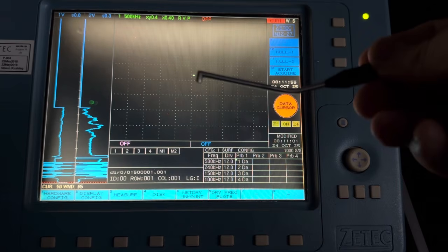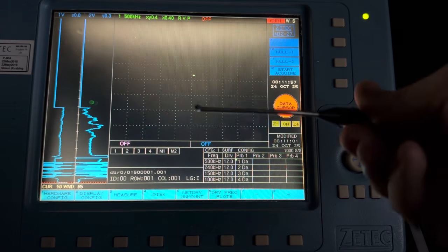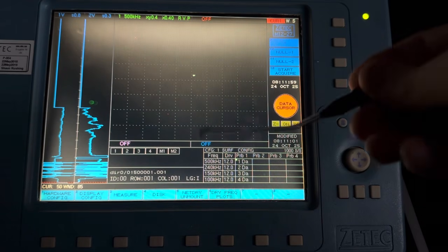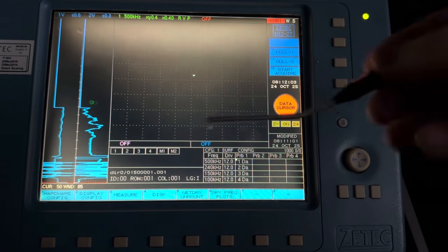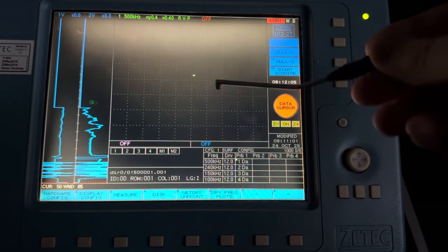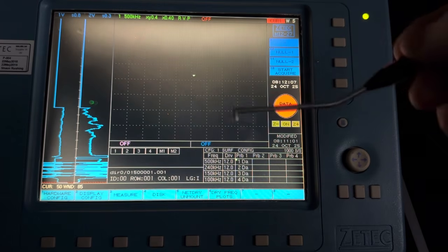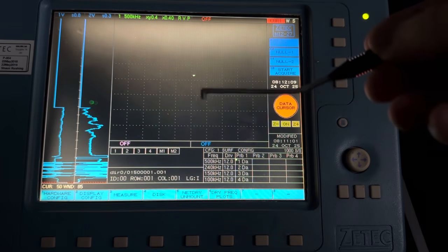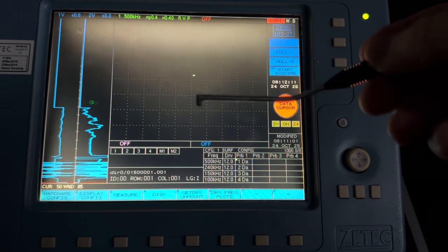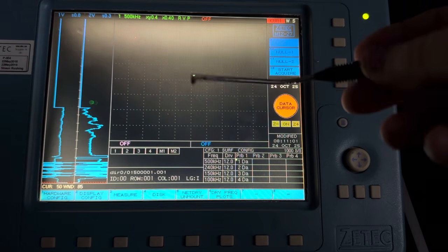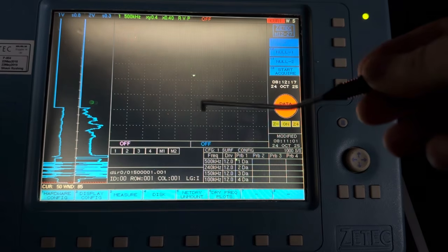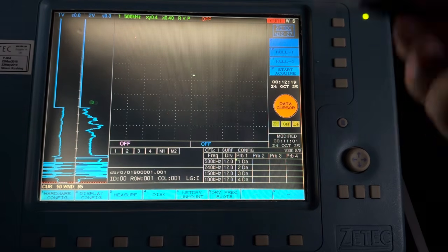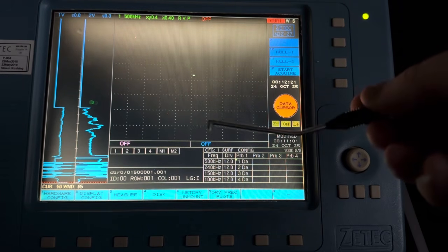for discontinuities. But with a pancake coil, as long as you're scanning properly with 100% coverage and you're hitting potential flaws from different angles of attack with your coil, you can find indications, or you can find discontinuities in any orientation: circumferential, axial, volumetric. That's nice about pancake coils, as long as you have complete coverage.